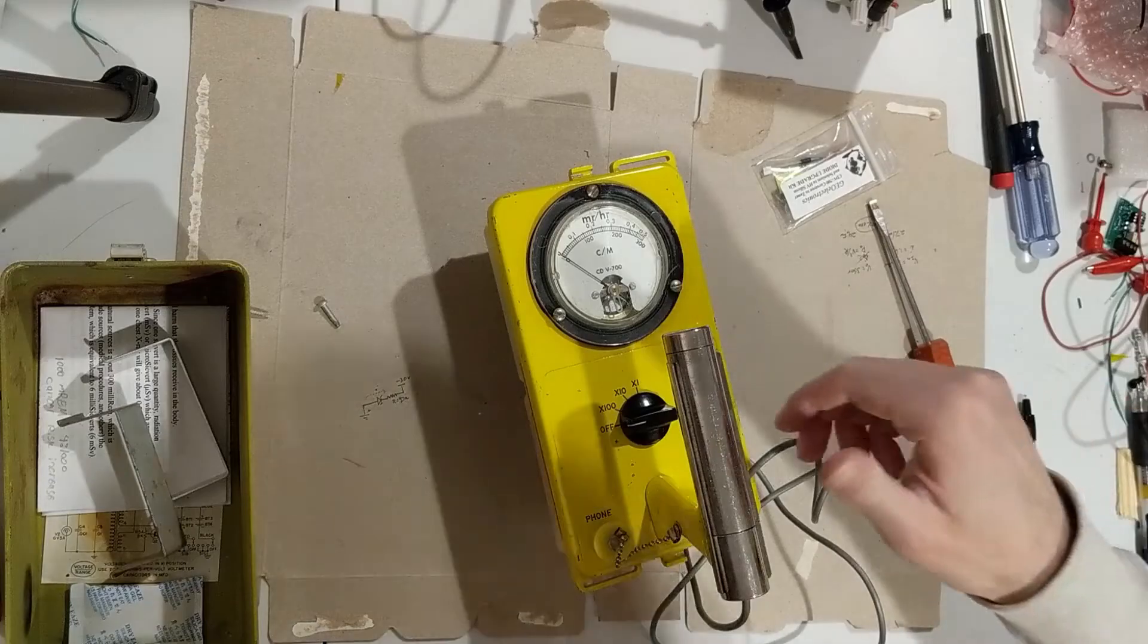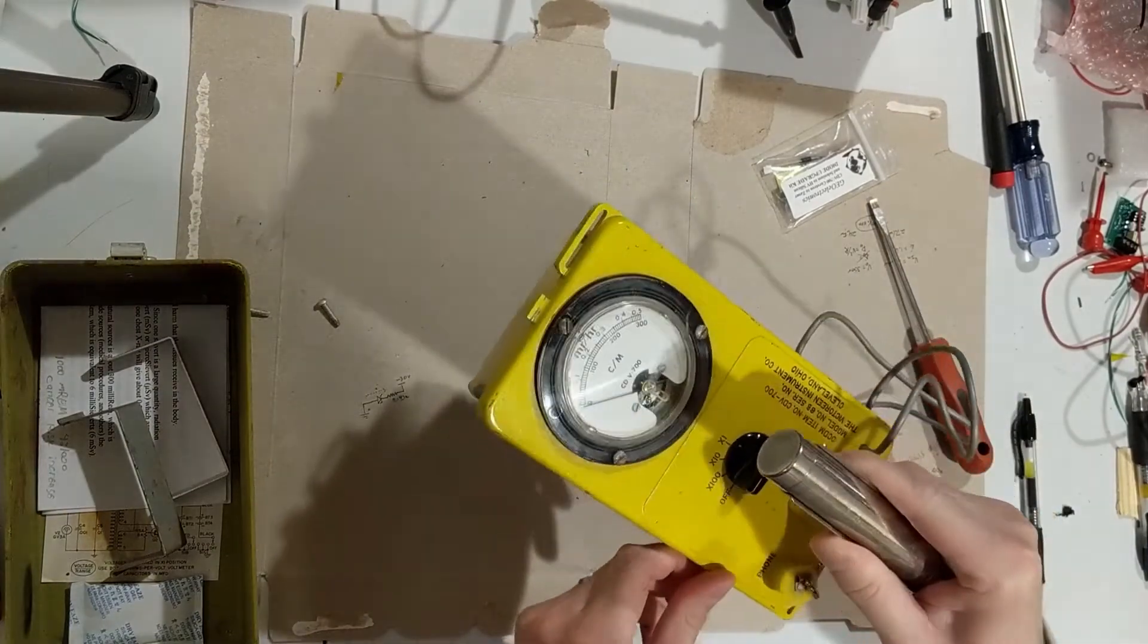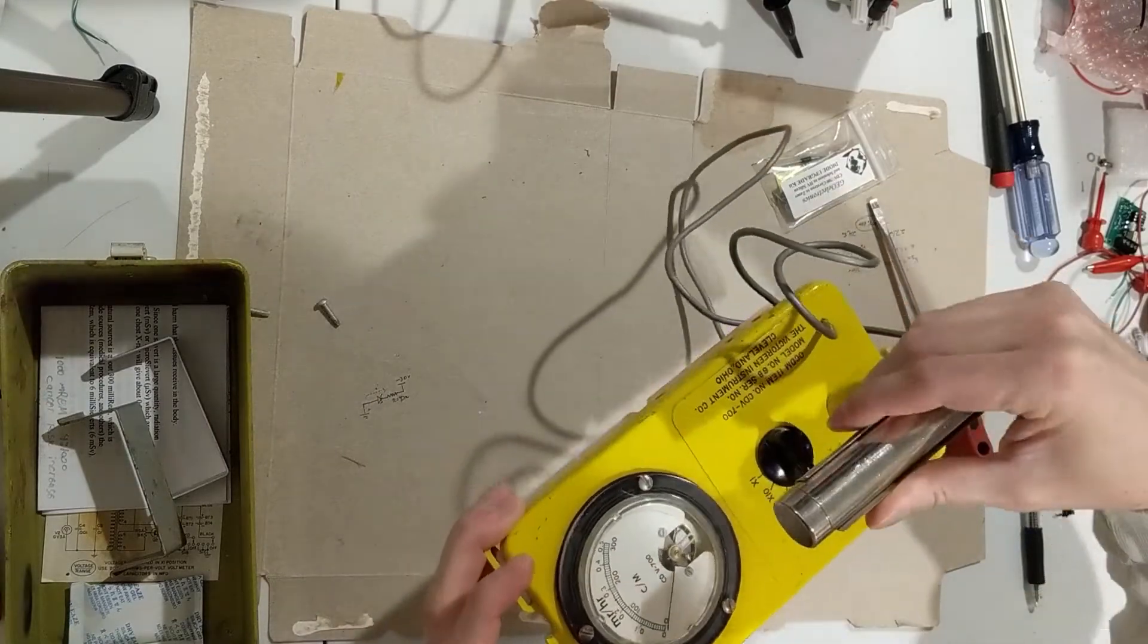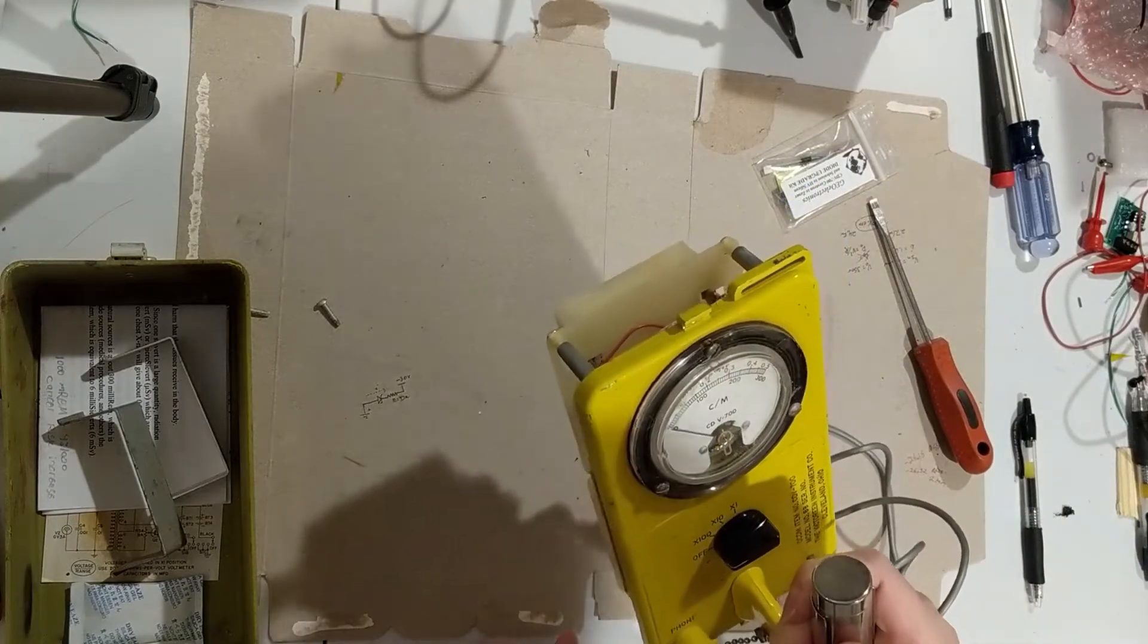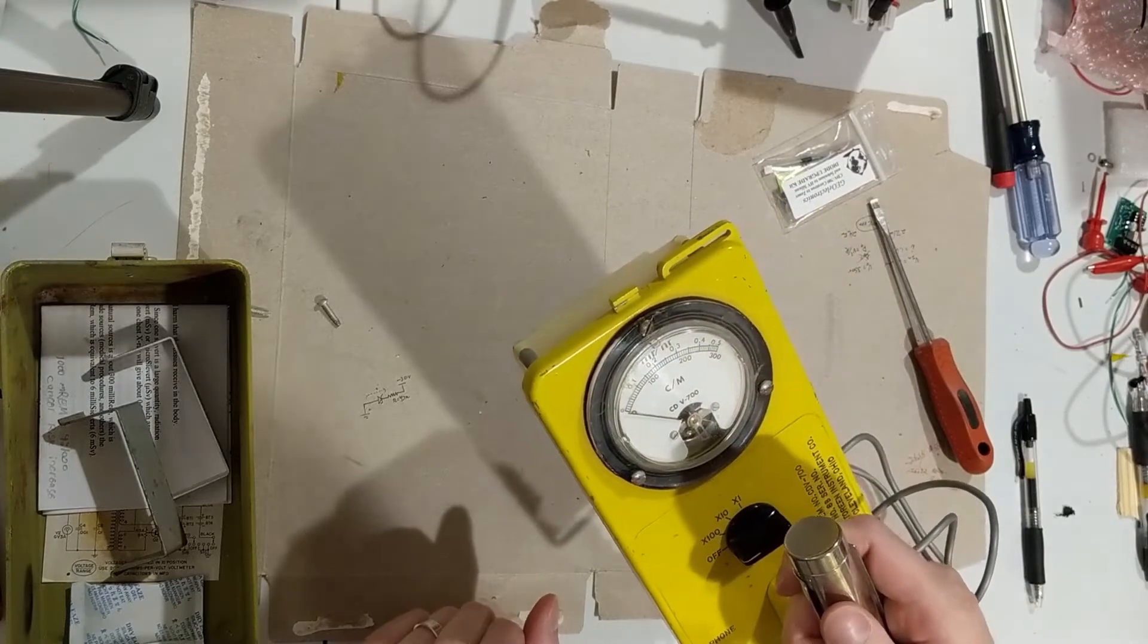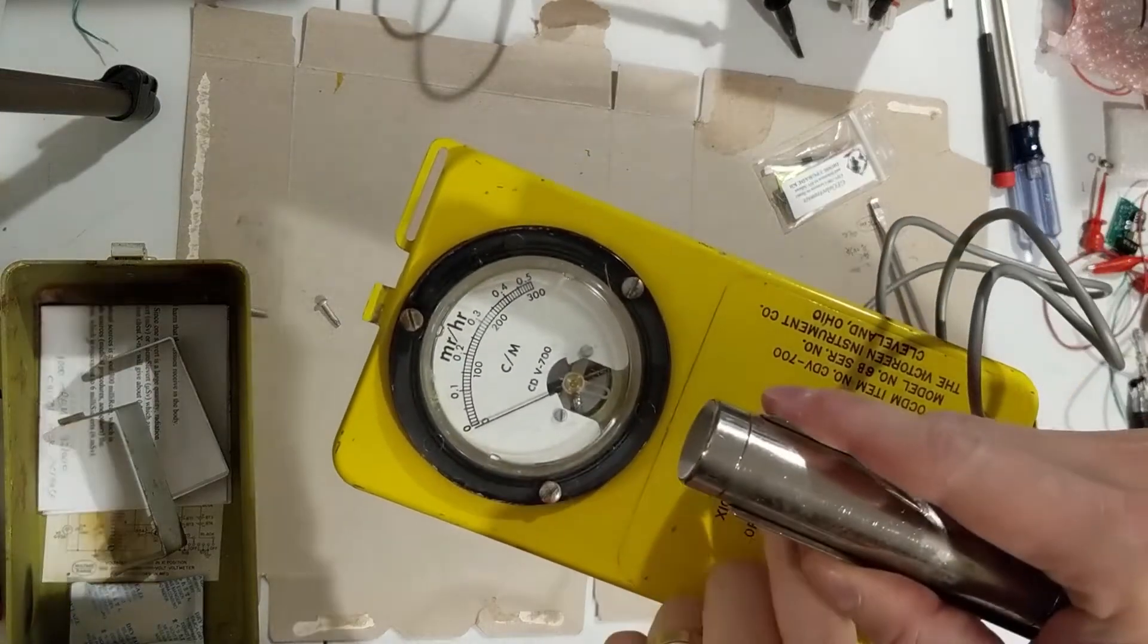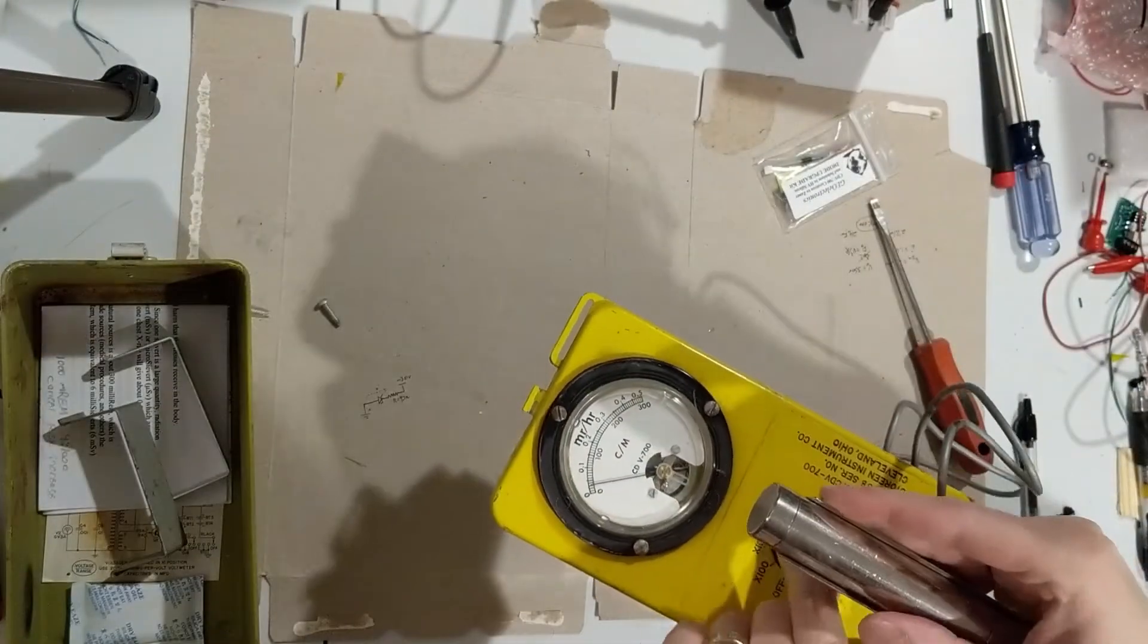Hey everybody, here I have my Victoreen 700 survey meter Geiger counter. The problem I started having with it is when I turn it on, it starts making a medium to high frequency buzzing noise and the meter starts reading full scale. I'll see if we can hear it in the video here. You can see the meter starts creeping up relatively quickly.